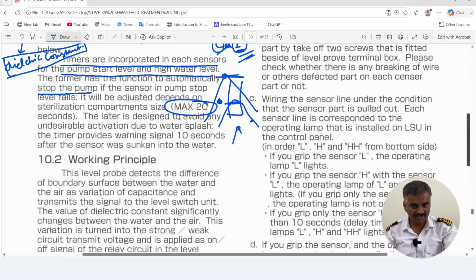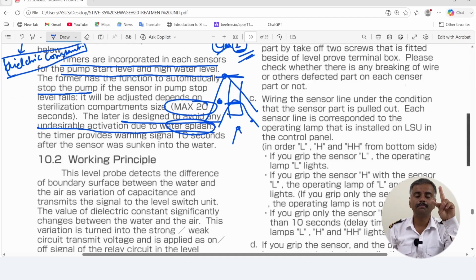Okay, the timer is designed as such to avoid any undesirable activation due to water splash. So there are two purposes for which the timers are designed. One is that the pump does not keep on running even if there is no suction coming, because, say, the pump is clogged or there is a failure of the pump components, due to which suction is not coming and the high water level is not reducing. If the high water level is not reducing, the pump will continuously keep on running to reduce the tank level, right? But your pump will get damaged, it will get heated up, because it's not meant to run continuously. The pump is in auto, so there should be a timer to make sure that for a set period of time the pump starts and then stops within that period of time, within 20 seconds.